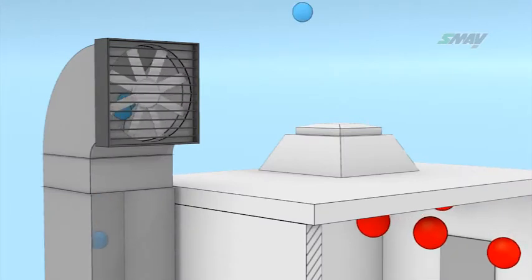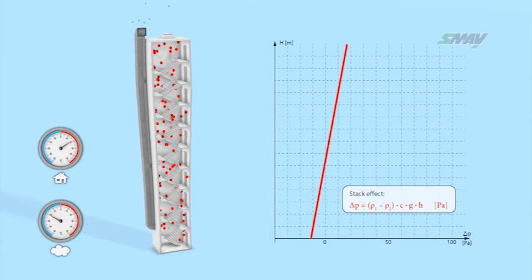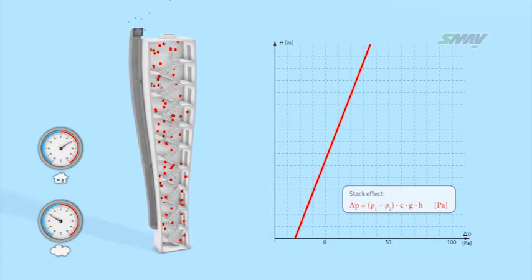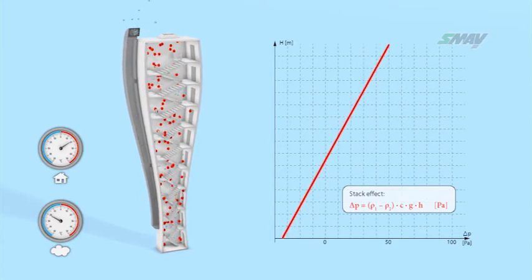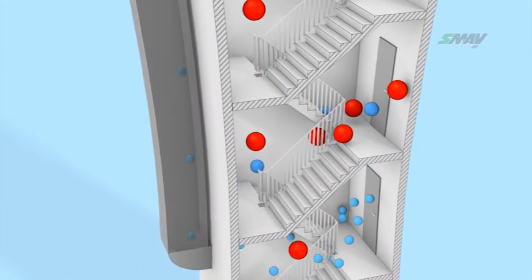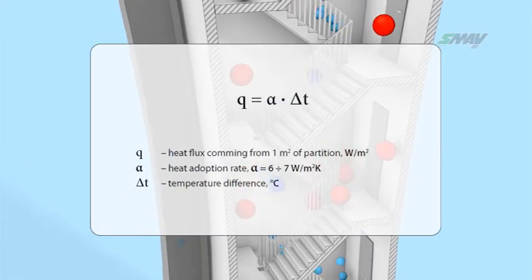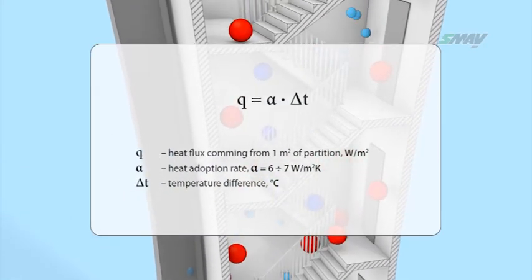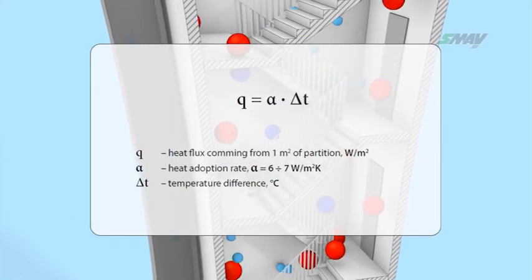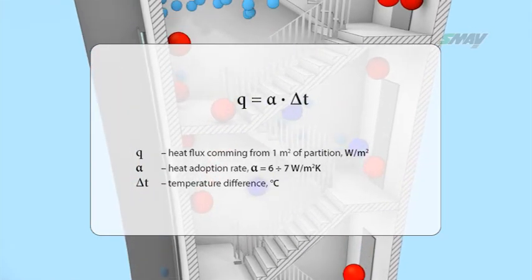However, if for that same system, air is supplied to the stairwell at a temperature significantly below that of the inside, then a pressure gradient will occur as a result of the stack effect. The stack effect occurs due to the heating up of air particles by walls and stairs, and the amount of heat dissipated by the walls is proportional to the difference in temperature between the air and the partitions.